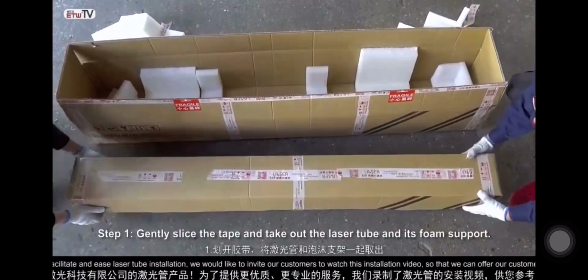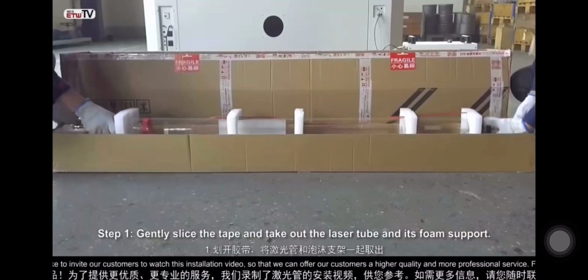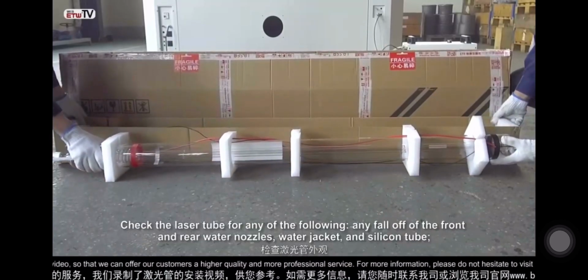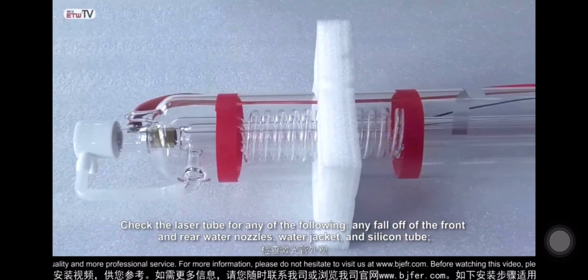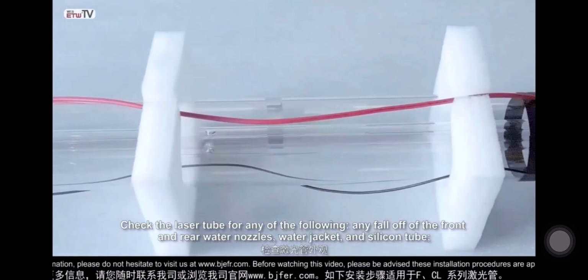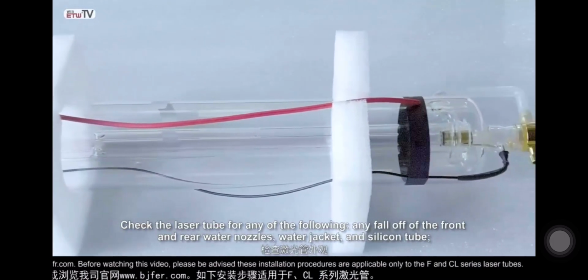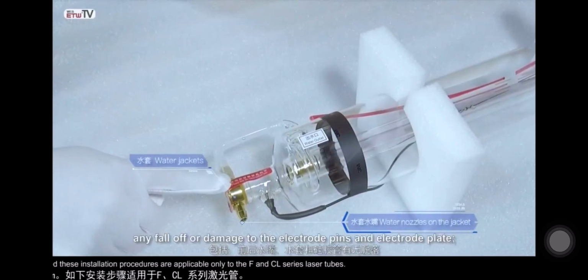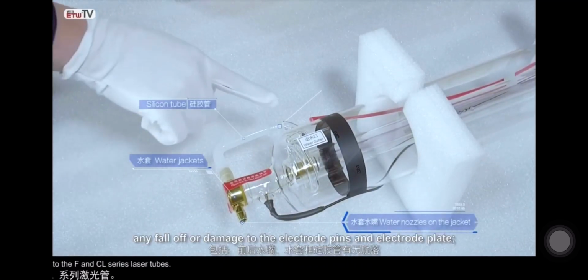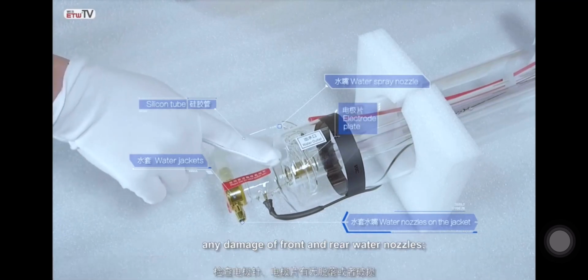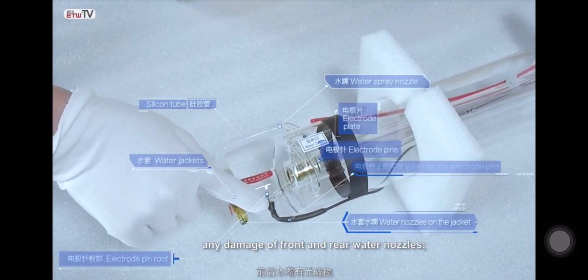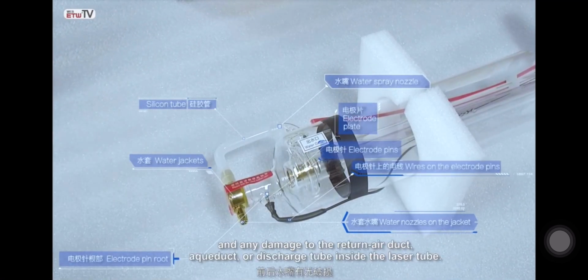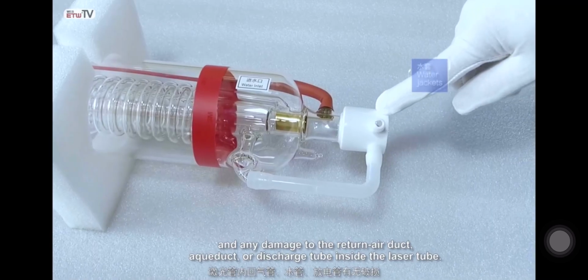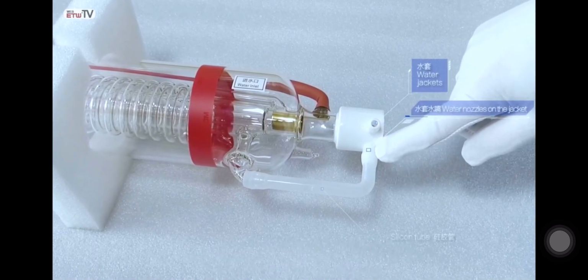Step 1. Gently slice the tape and take out the laser tube and its foam support. Check the laser tube for any of the following: any fall off of the front and rear water nozzles, water jacket, and silicon tube, any fall off or damage to the electrode pins and electrode plate, any damage of front and rear water nozzles, and any damage to the return air duct, aqueduct, or discharge tube inside the laser tube.